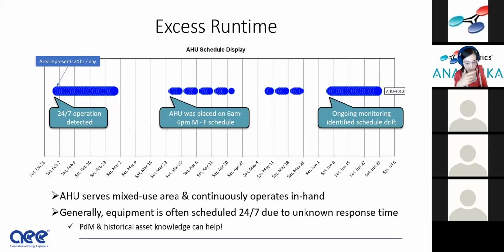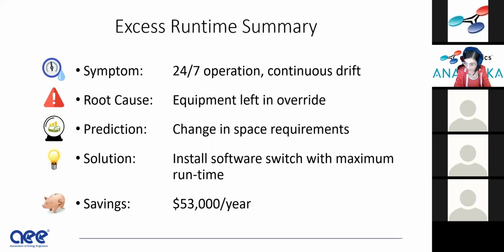And another local customer, they had a gym that was operating 24/7. And the contractors and the team worked so hard to prove that we might not need that unit to run 24/7. I did a savings calculation to show them how much they would save. I think they installed occupancy sensors to actually prove that people weren't using the gym 24/7. So given that in the past it has been, oh yeah, that needs to run 24/7, we can help facilitate a conversation about, has something changed? You want to test it? You want to test this time and let it run a few days, look at the response time. Here we actually had to install a software switch with a maximum runtime because of the change of space requirements. Anyway, long story short, that's about a $50,000 a year issue. I've been supporting people too recently with COVID shutdowns.